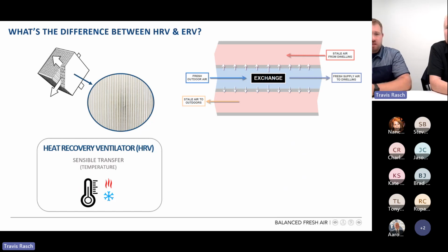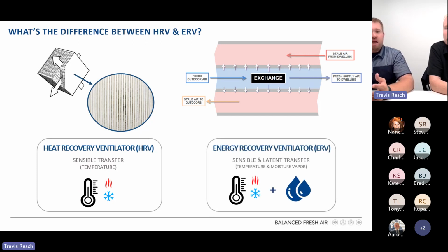So when we talk about this exchange, the first is a heat recovery ventilator, or HRV. An HRV simply does a sensible transfer. So we're simply dealing with temperature. What's the temperature of the incoming air? What's the temperature of the air that's going out? What am I going to expect for that tempered air to enter after it goes through the HRV? An ERV, or energy recovery ventilator, has both that sensible piece as well as a latent transfer, moisture vapor. So we have added an additional component. Not only are we going to get the benefits of a sensible transfer, making that outdoor air and our indoor air work with one another, we're also going to get a moisture vapor piece.